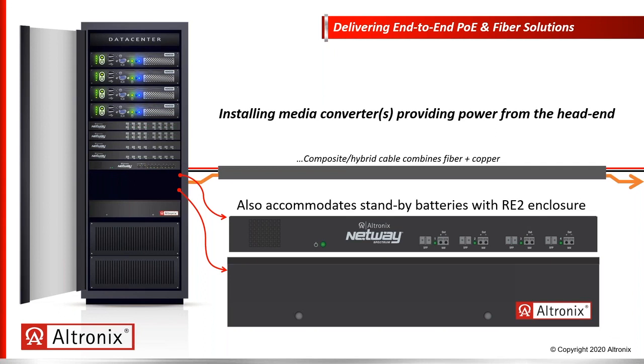Often the IT department will say their IT racks provide battery backup, from manufacturers such as APC or Minuteman. But that battery backup is designed to keep the rack equipment powered, not necessarily the edge or connected devices, and typically only for a short period of time. Utilizing our power sourcing equipment with battery backup gives you the ability to deploy a system that's mission critical, even for longer term AC power failure.